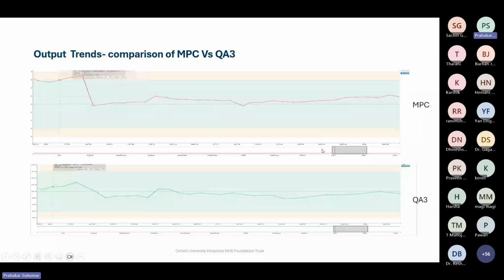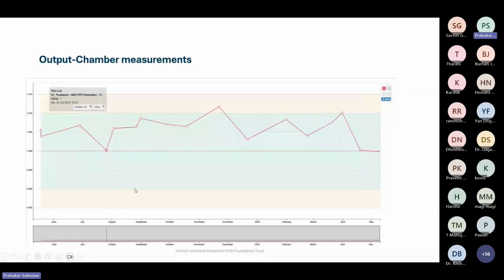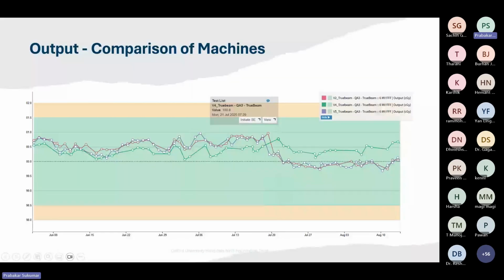And this is compared against the chamber measurements, which we do monthly, rather than weekly chamber measurements we will be transferring, so you will get confidence on what you are measuring with MPCs and QA3. We cross compare against the output measurements, and then in QA Track Plus, we can compare different machines, how each is performing.